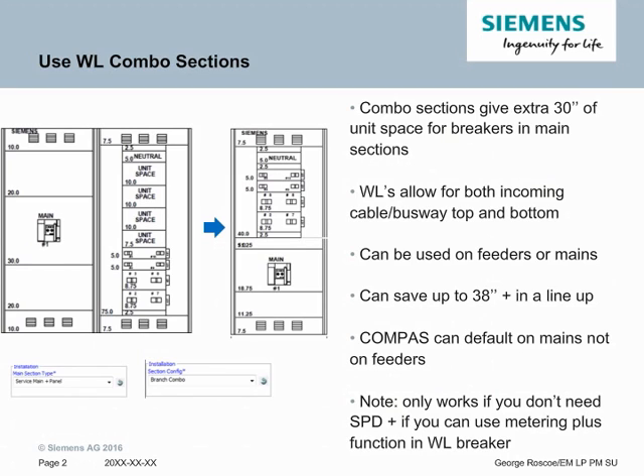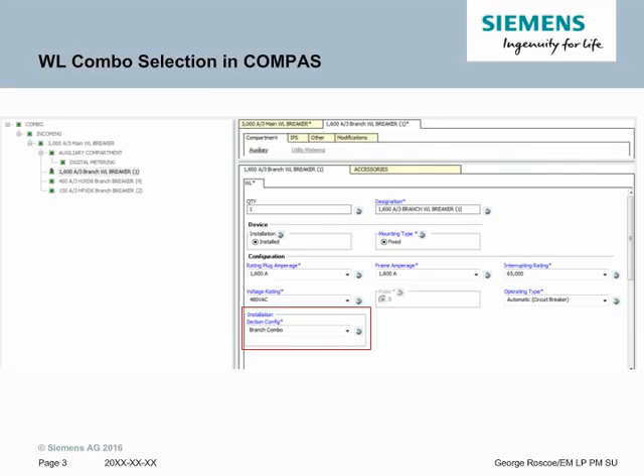In order to have COMPAS use this design, which is default for mains when possible, use service main and panel selection for mains and the branch combo option for feeders. This option drop-down is available under the WL breaker section tab. As a note, using combo section works if you can either group mount the surge protected device or utilize the metering plus function of the WL. If you need to use a PAC meter or other meter, you will need to use the standard section for WLs, not the combo section. The selection for WL combo sections is under the WL main tab, as illustrated in the image. The example here shows where the option is for feeder WL breakers, namely under the section config option dropdown.